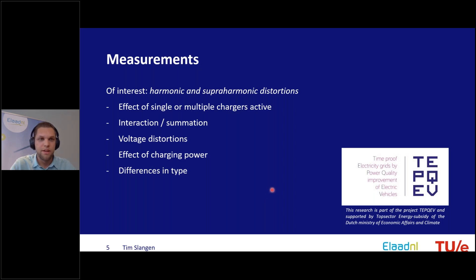The main research interests in the measurement campaign were harmonic and supraharmonic distortions. We looked at both effects of a single charger active and multiple chargers active, and whether there are interactions and summation in harmonic or supraharmonic distortions. Important also is what happens to the voltage, which matters to grid operators, and any resonances in practice. The effect of charging power also matters — chargers are not always used at maximum power, as vehicles capable of 350 kW are quite limited currently. All this research is part of the TEPQEV project.